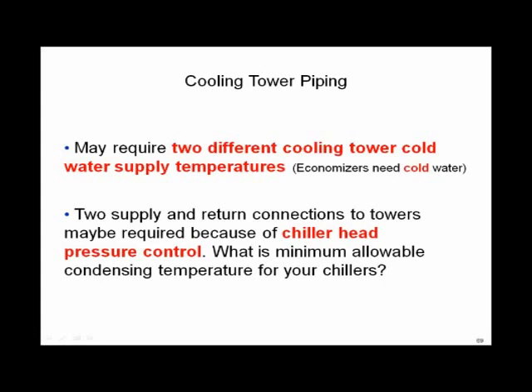You may need 2 different cooling tower cold water supply temperatures. Wow, what am I trying to tell you? Waterside economizers, ladies and gentlemen, want the coldest water you can get. But the second paragraph, that gives you a hint. If you have a centrifugal chiller, it may not want water that cold. In fact, most of them don't. Now, this is a generic statement. We're not talking brands here. But you need to go to your particular chiller manufacturer and say, listen, I've got to do a waterside economizer. How cold of water do I put to your condensers?